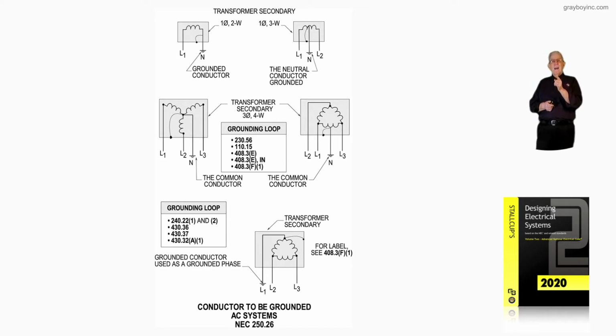But notice that high leg, L2, is going through a 240-volt coil, 120 to the left. To the right-hand side, and using that coil, you're going through 240 to 120 to ground. And as I said earlier, 240 plus 120 divided by 1.732 is 208 volt. And typically, that's the high leg. Now notice all the sections that you have to look at to really get a good feel for that high leg and what's required. Look at the grounding loop.